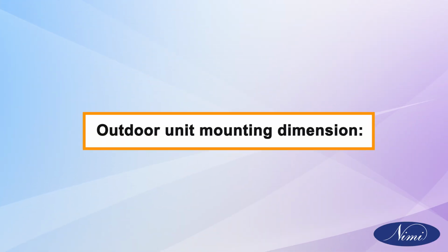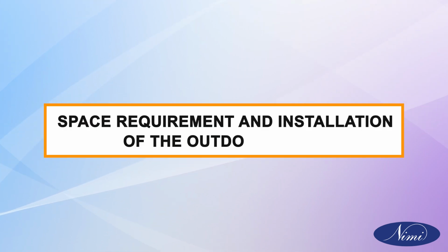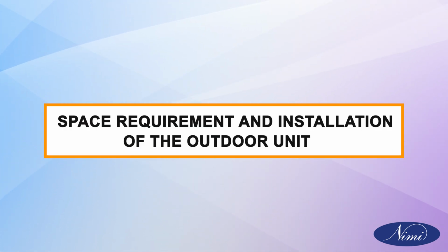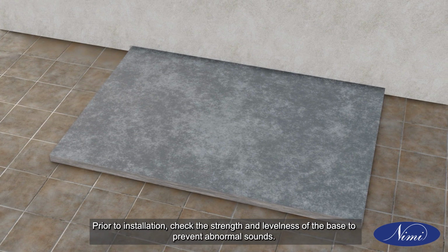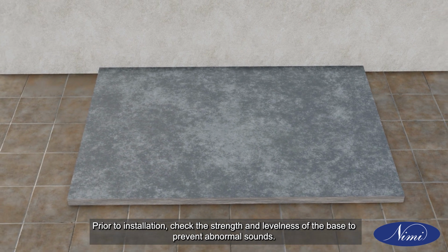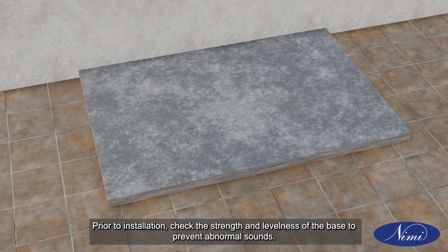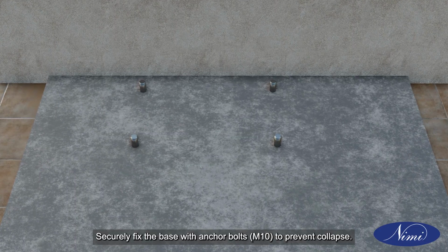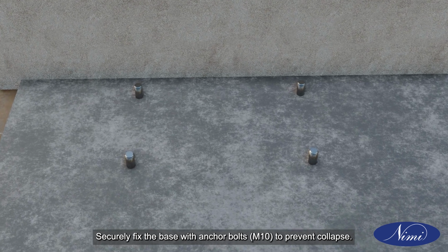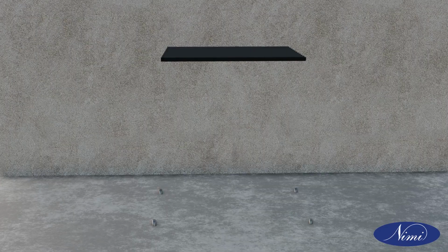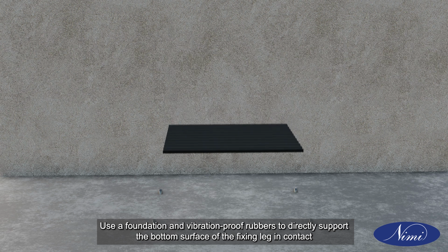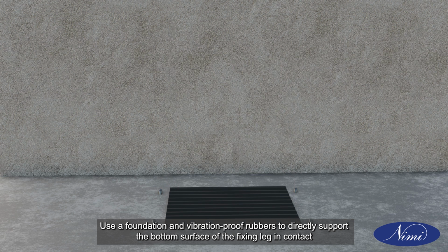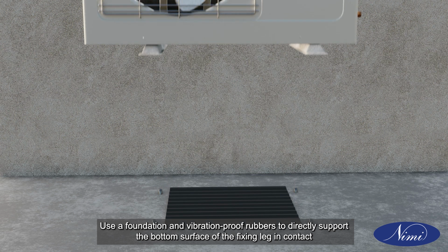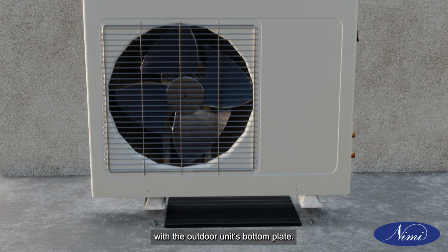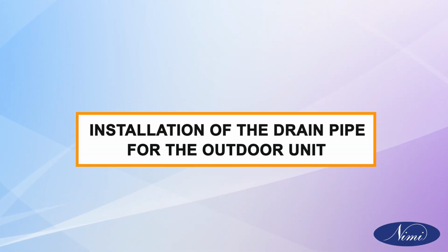Outdoor unit mounting dimension. Space requirement and installation of the outdoor unit. Prior to installation, check the strength and levelness of the base to prevent abnormal sounds. Securely fix the base with anchor bolts, M10, to prevent collapse. Use a foundation and vibration-proof rubbers to directly support the bottom surface of the fixing leg in contact with the outdoor unit's bottom plate.